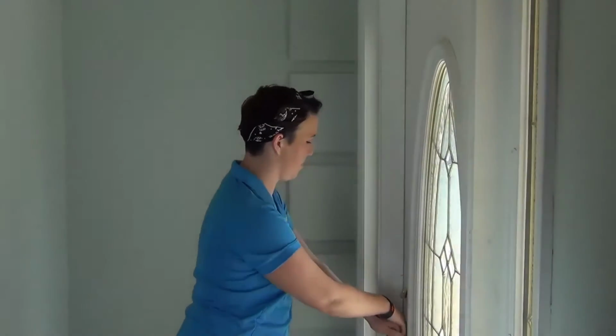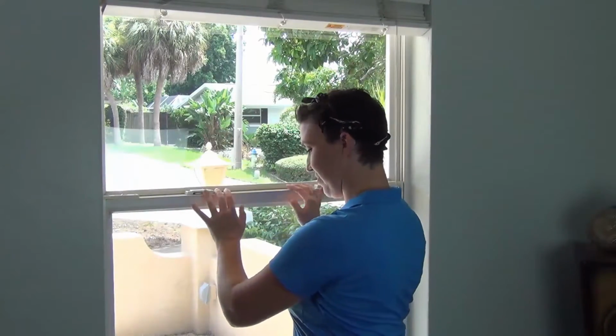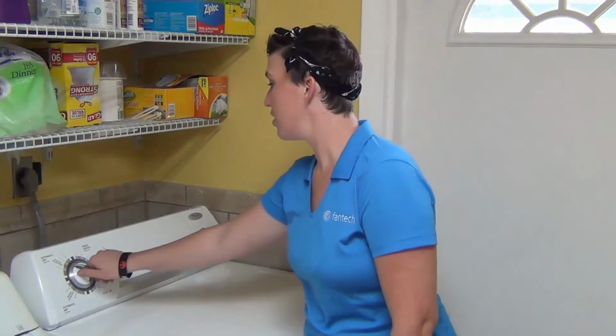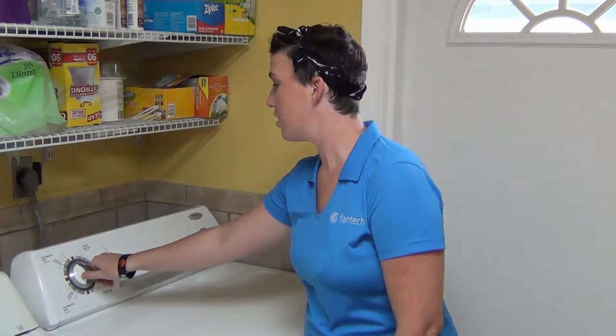Prior to running the system, it is important that all exterior openings, like doors, windows, and if you have a fireplace, the flue damper is closed. Switch off any system that exhausts or supplies air from the outside, such as clothes dryers, bath fans, HRVs or ERVs, vented microwaves, heating and cooling appliances, and the like.